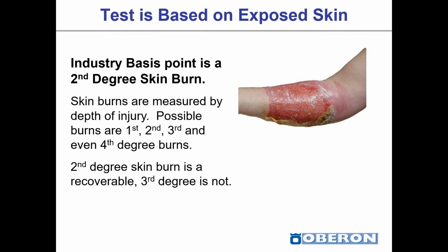The testing that we run in terms of certification and the creation, so the R&D behind Arc Flash PPE, is based on exposed skin. So the industry basis point for a second-degree skin burn, again, is 1.2 calories. I mentioned previously how the depth of injury is the actual degree of the burn. We have 1st degree all the way through to 4th degree burns. A second-degree skin burn is recoverable. We can actually rub some cream on there. There are treatments that we can use, but a 3rd degree is not.